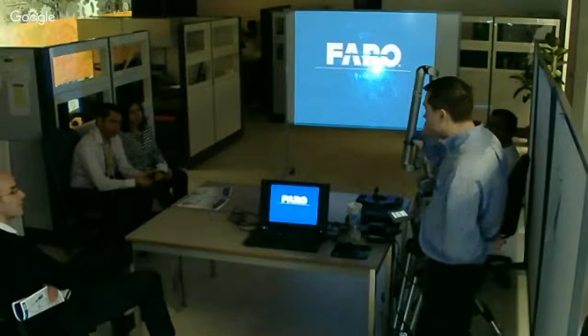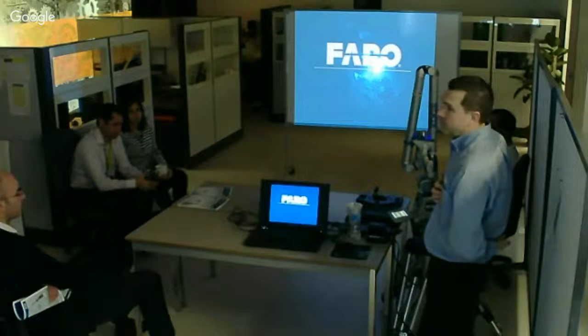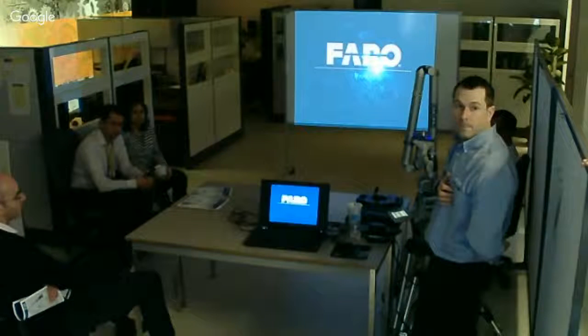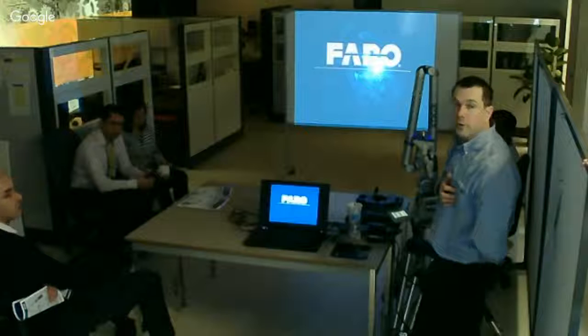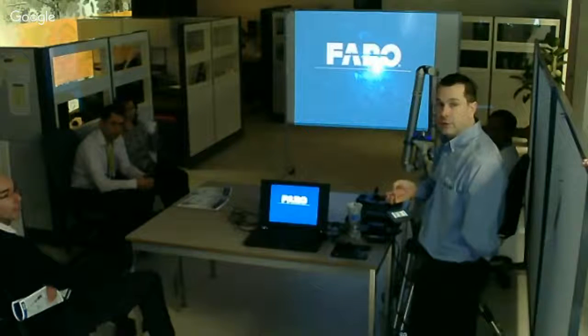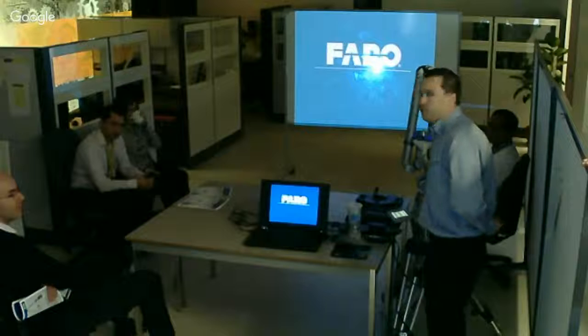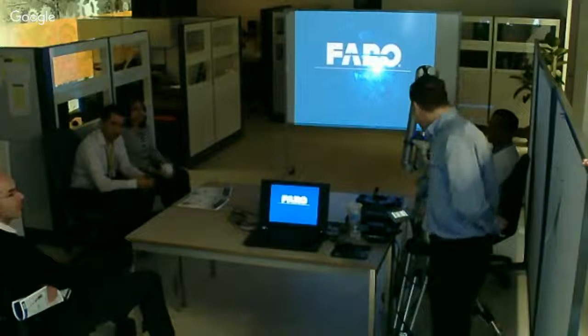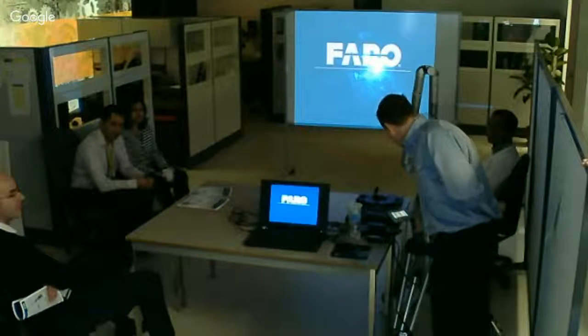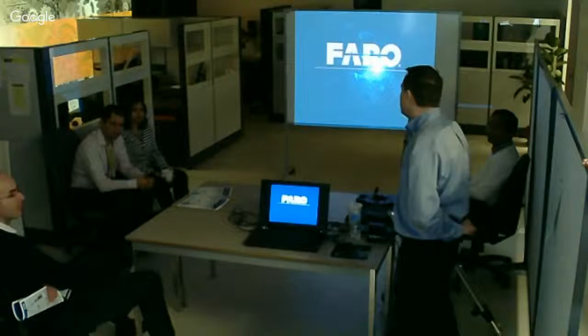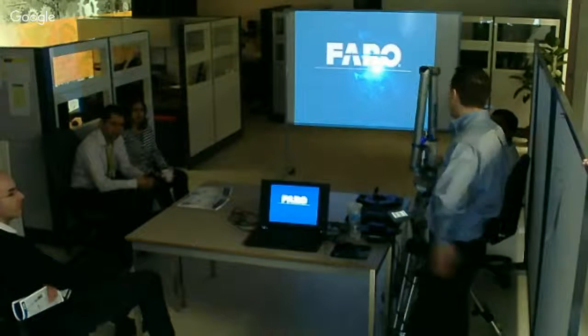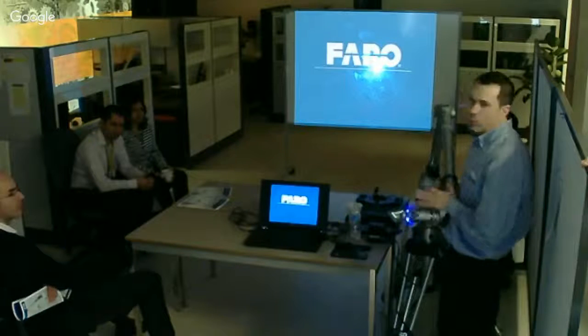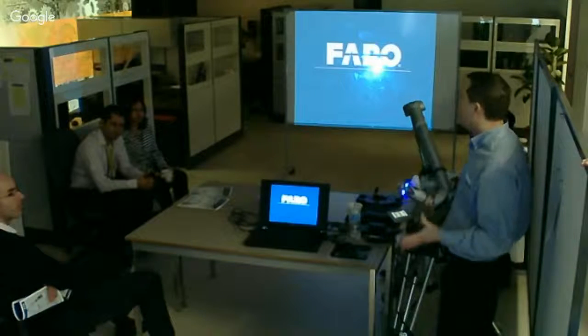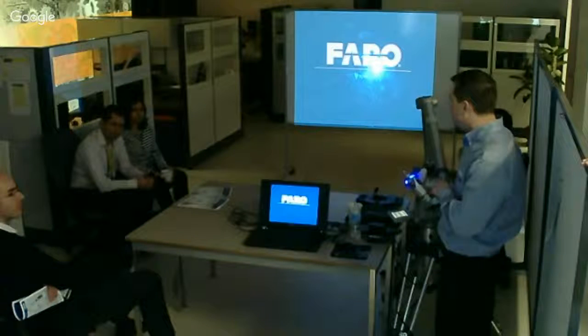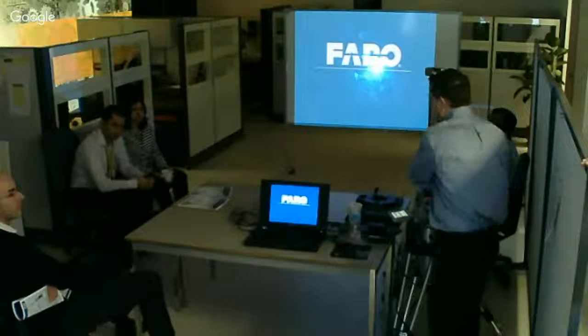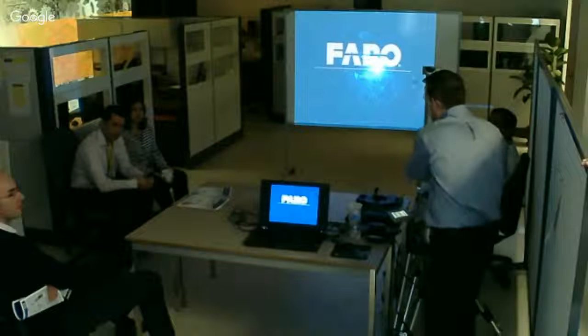But do we have any questions specifically? Anything I went through there? How good is the cloud data? In what regards, how good, like the accuracy? This arm, and there are different sizes, as you can see in the brochures. This arm has an accuracy of 0.029 mm, so just over 1 thou, and then when you add a scanner, the scanner adds about 1 more thou to it. So again, depends on which arm size, but it always adds about 1 extra thou. So this arm setup would be around 2 thou accuracy, plus or minus.